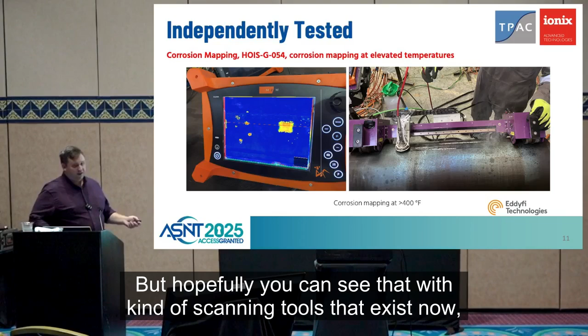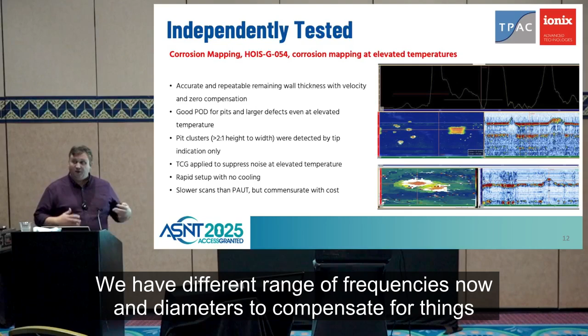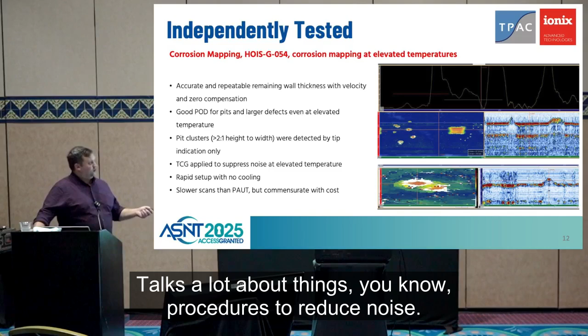But hopefully you can see that with the scanning tools that exist now, we can get data that's as good as ambient temperature. This is taken at above 400 Fahrenheit. And there's some good advice and recommendations on things like which couplants to use, how to do the compensations, do the zero corrections, and then advice on things like the probability of detection for certain pit aspect ratios, defects. And you'll see, we've taken some of that on board. We have different range of frequencies now and diameters to compensate for things like pitting and other areas. Talks a lot about procedures to reduce noise.